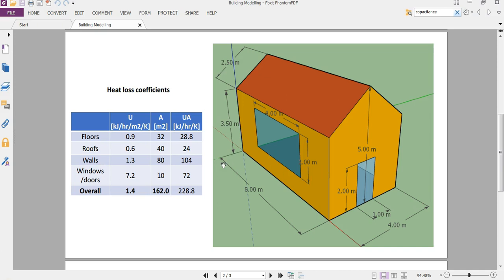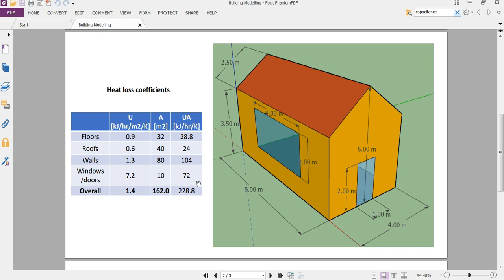So here I've estimated some U values for each of the surfaces, and based on these dimensions for this building, we have the areas for each of these surfaces. That will give us an overall UA value, and then a total UA value for the whole building and a total surface area, which we'll also use.